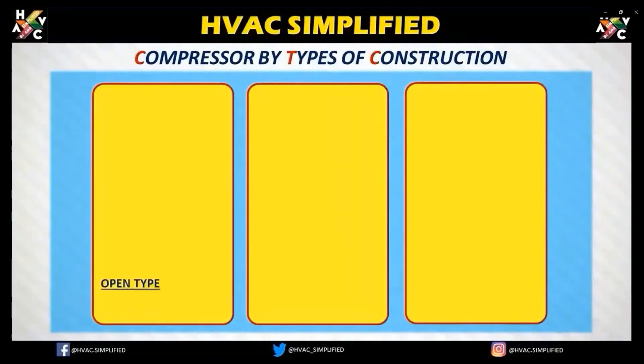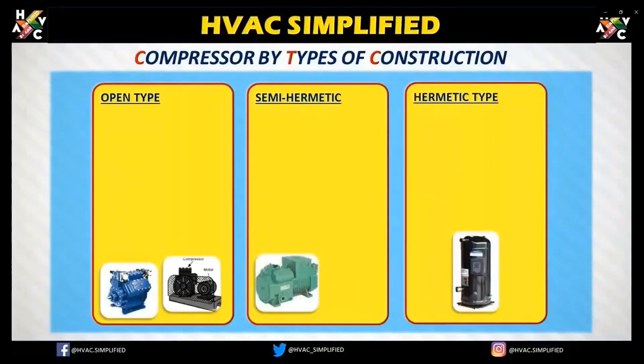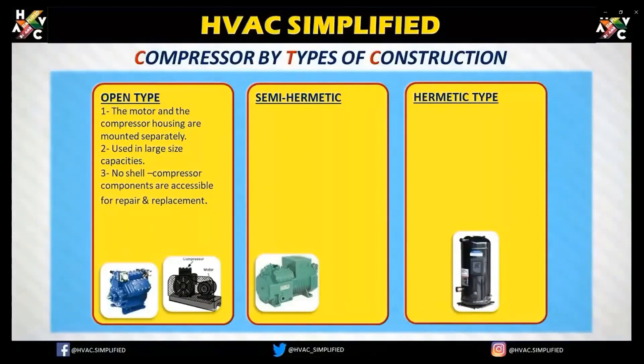Now let us see the types of compressor construction. There are three types: open type, semi-hermetic type, and hermetic type. In an open type compressor, the motor and the compressor housing are mounted separately, used in large size capacities. The compressor components are accessible for repair and replacement.